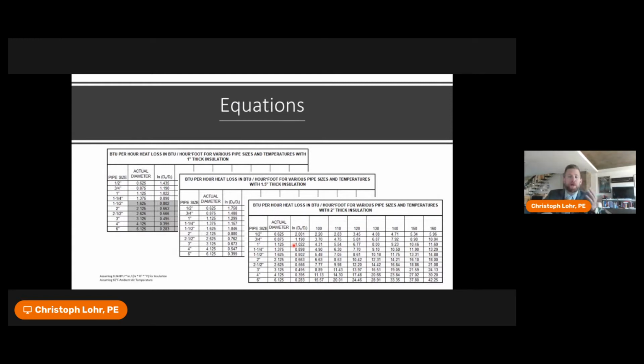All right, so the first one that I mentioned before is 30 BTU per hour per lineal foot, which is a really bad assumption and is one that's being used in the industry currently that should be done away with. Why is that? Well, when you actually calculate heat transfer rate per lineal foot, based on fluid temperature and different pipe sizes varying due to insulation thicknesses, you'll notice that you don't even get close to that 30 BTU value until you get either a 4-inch pipe at 160 degrees Fahrenheit or a 6-inch pipe at 130 degrees Fahrenheit.